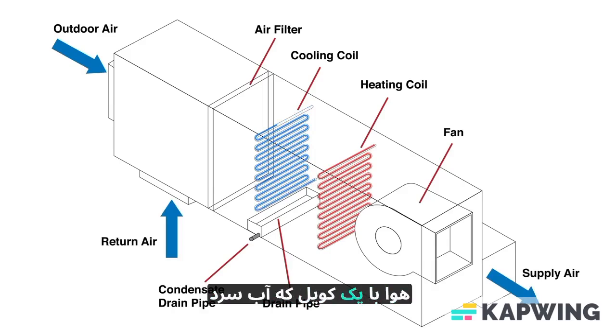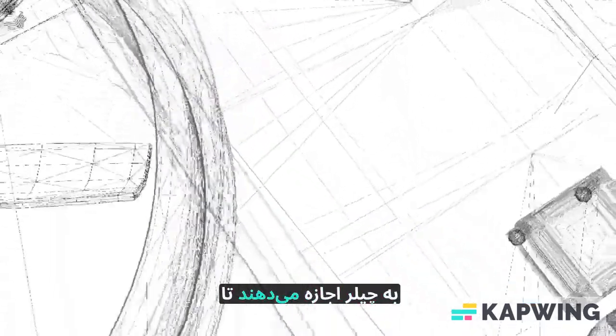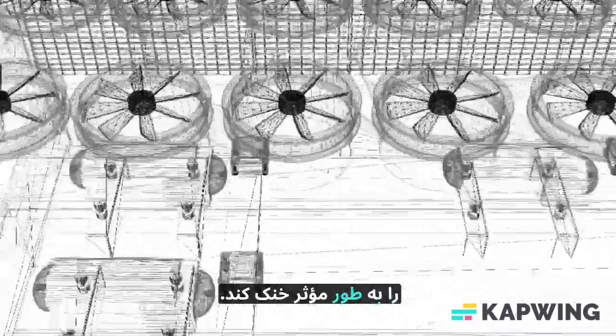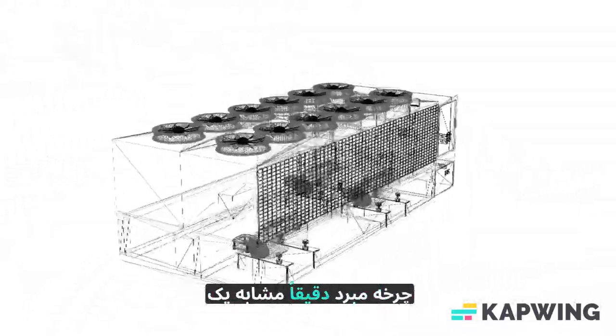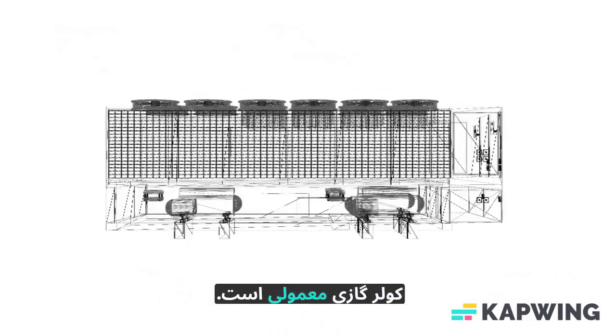Inside the air handler unit, air comes into contact with the coil that runs the chilled water. Much like how an evaporator cools water inside a chiller, the coil cools down the air that eventually enters the open space of a building. The chilled water, now warmer from the absorbed heat, returns to the evaporator to be cooled down once again. These are the mechanisms that allow a chiller to efficiently cool down mid to large-sized buildings. The refrigerant cycle is the exact same as that of an ordinary air conditioner, but the general efficiency of a chilled water system makes it better for larger buildings.